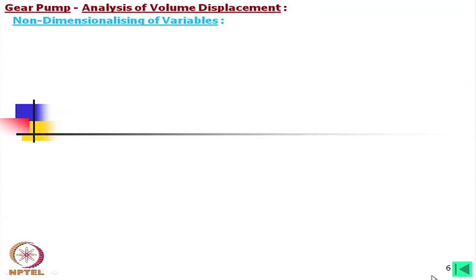Now we shall try to find out the volume displacement. If we can calculate the variation in this area with shaft rotation or with respect to time, then we can multiply by the width of this gear. In the case of a piston pump, we multiply a constant area with the variable stroke length. In the case of this gear pump, the area is varying and the width remains constant. So if we can analyze the variation of area with shaft rotation, we can easily find out the volume displacement and then the flow rate.